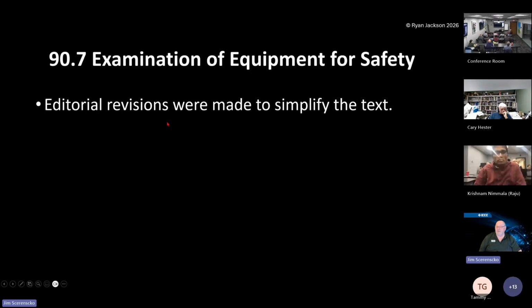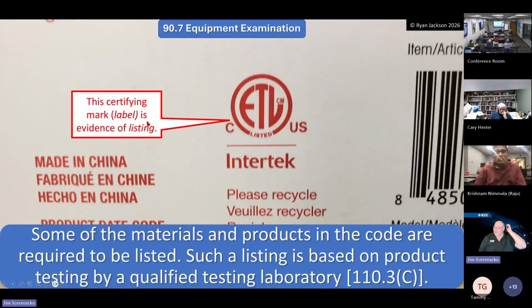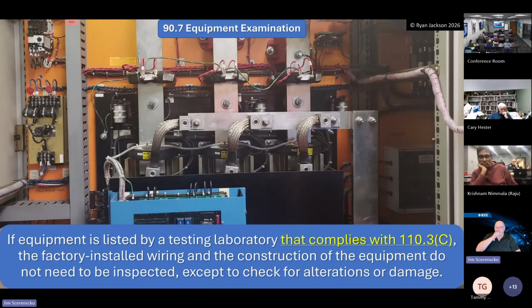90.7 is the examination for safety of equipment. We want to make sure that, and right now the market is flooded with counterfeit stuff and overseas stuff. It is just terrible. We run across more and more stuff every day where we have to tell them, hey, you got to go get the field evaluation done on this because it doesn't have a listing on it. We just had a guy screaming about a wire stripping machine that he bought for $10,000, and it cost him $15,000 to have it certified. If he'd just bought one in America for $25,000, it would have been all good. Anyway, it failed, I think, the first 3 times that they went out there. And there's a lot of counterfeit marks out there.